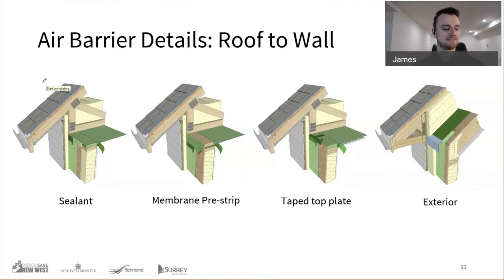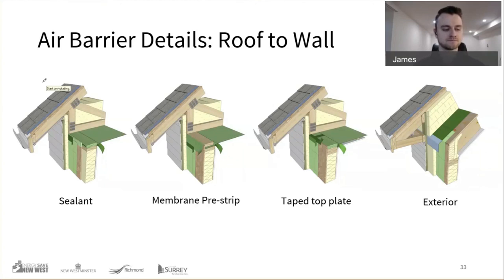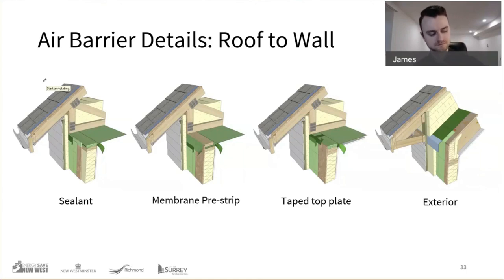A colleague from the City of Richmond adds a comment on mid-construction test scores: the City collects both mid-construction test scores and as-built scores, and this data suggests about a 25% gain after drywall is installed. That means if your final target is 3 ACH, your mid-construction test should not exceed 4 as a rule of thumb.